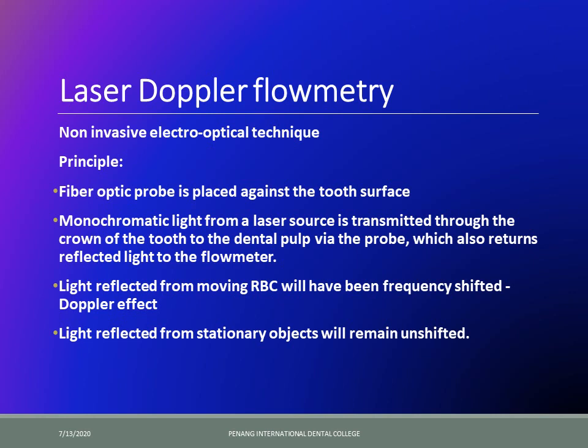Laser Doppler flowmetry uses an electro-optical technique. You place a fiber optic probe against the tooth surface, a light is shone from the laser and transmitted through the crown towards the dental pulp. This probe also returns the light which is reflected after hitting the dental pulp, back to the flow meter — the part of the instrument which evaluates blood flow.